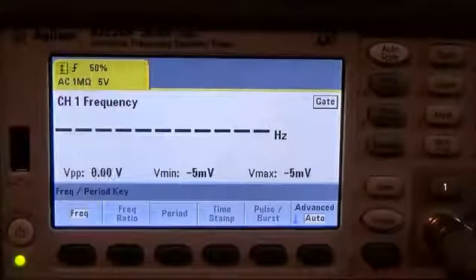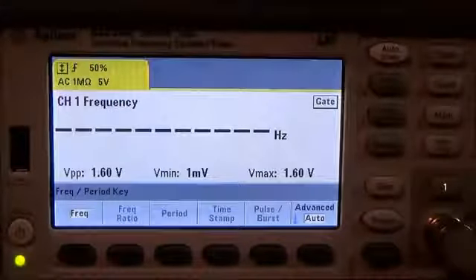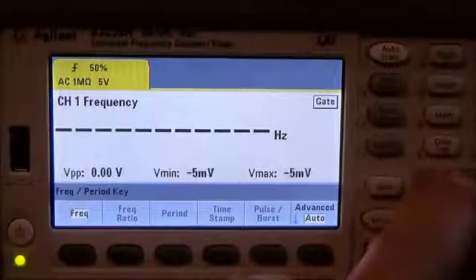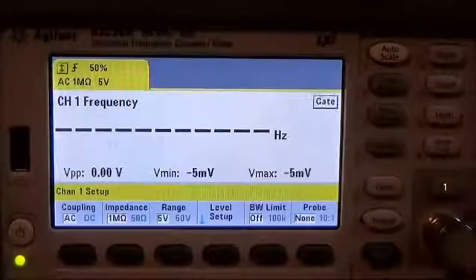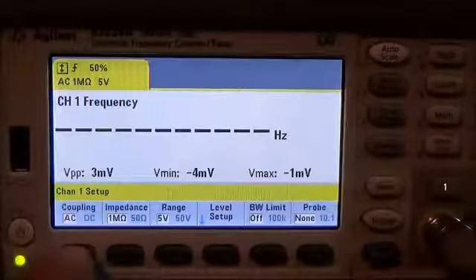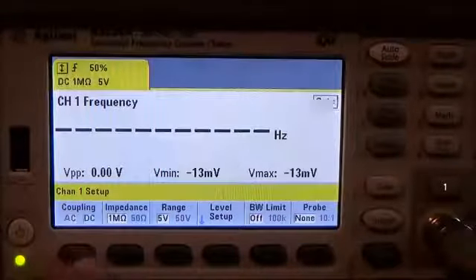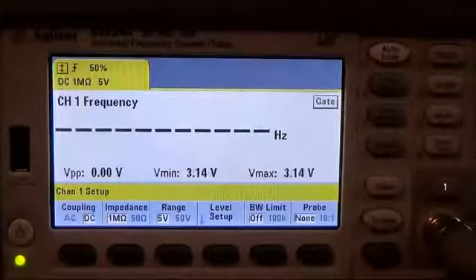By doing that we press channel 1 of the channel button. So press 1 here and then if you notice the soft keys here there's the coupling soft key. If we press that, that'll toggle between AC and DC. So we want to make sure it's DC.